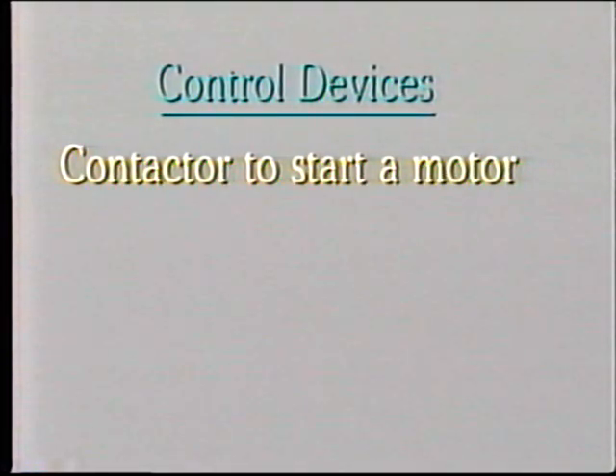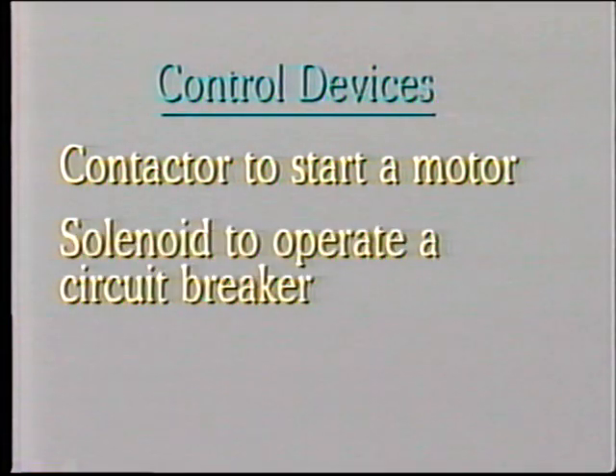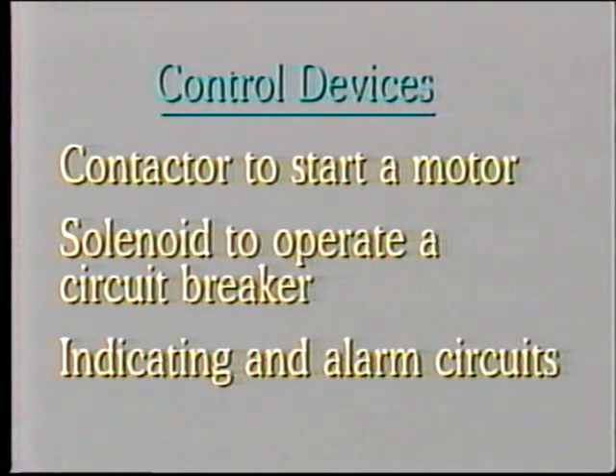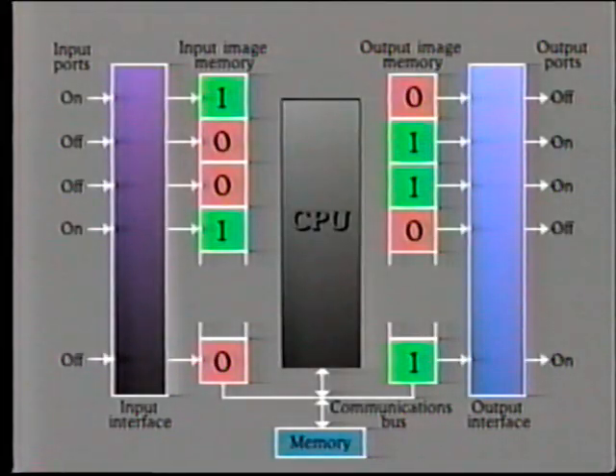Okay, so much for the input circuits. Now, let's move on to look at typical arrangements of output signals from the PLC. The function of an output signal is to energize a control device such as a contactor to start a motor, a solenoid to operate a circuit breaker, indicating and alarm circuits, and so on. The output module provides the interface between the CPU output image and the actual output terminals.